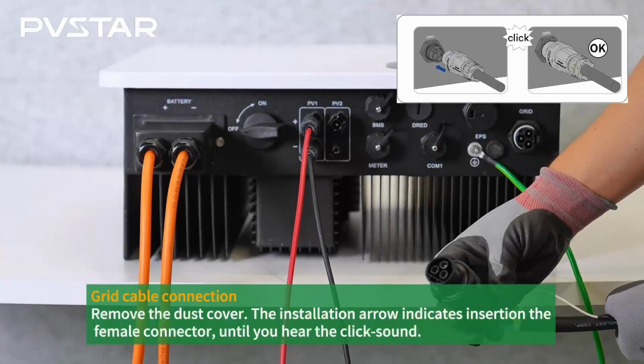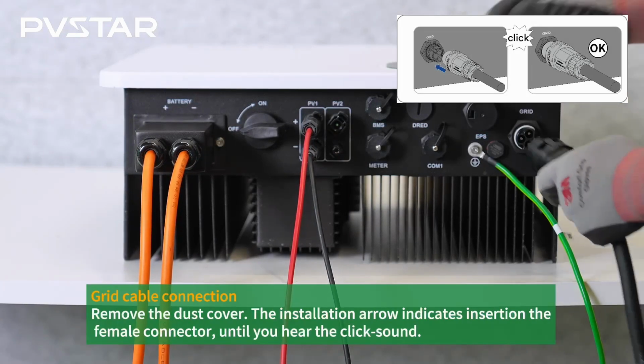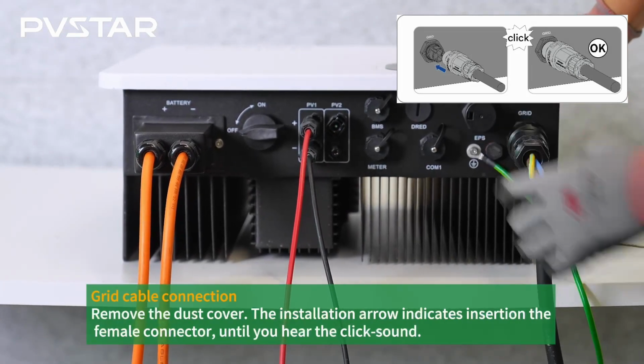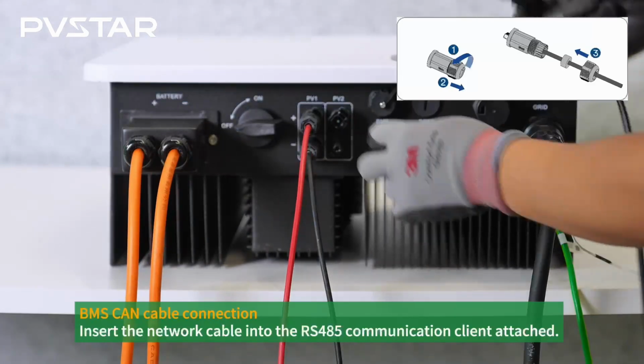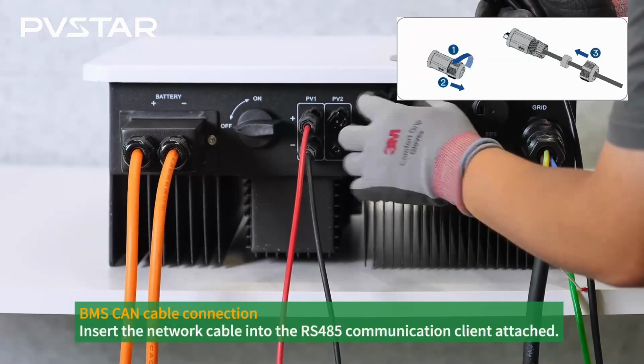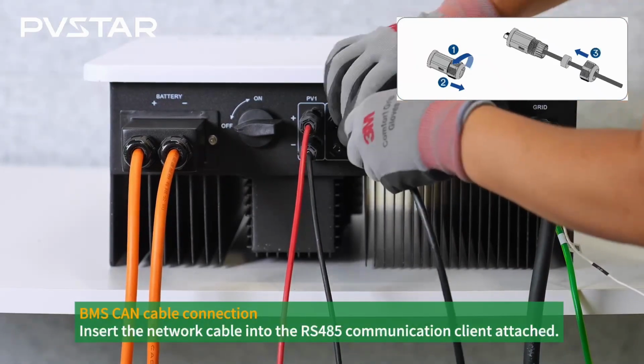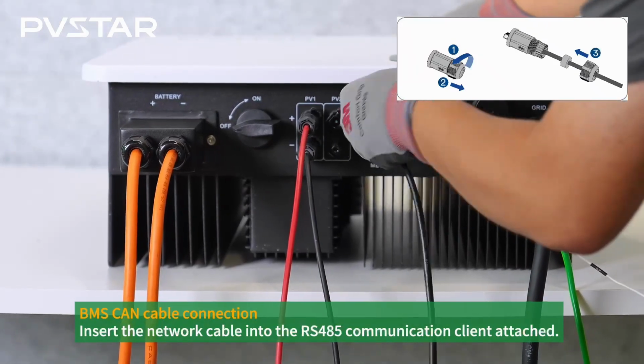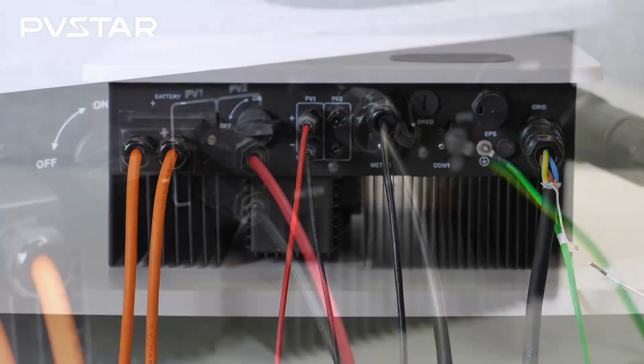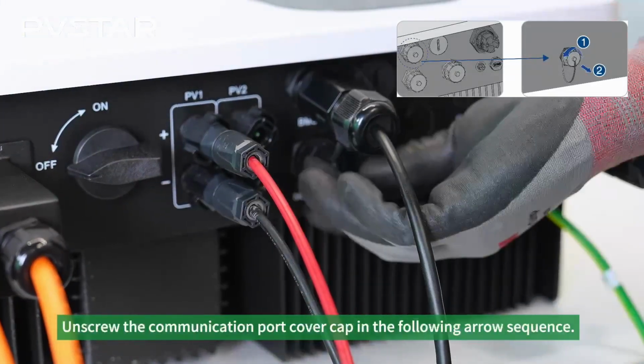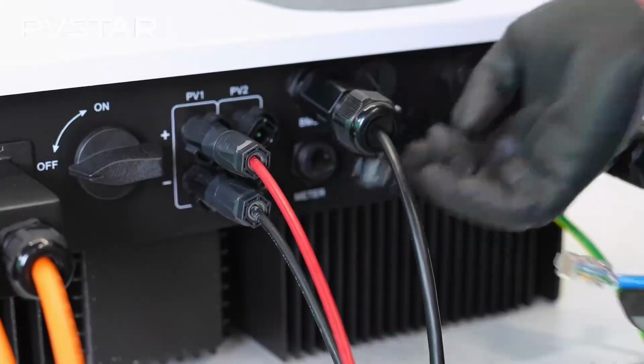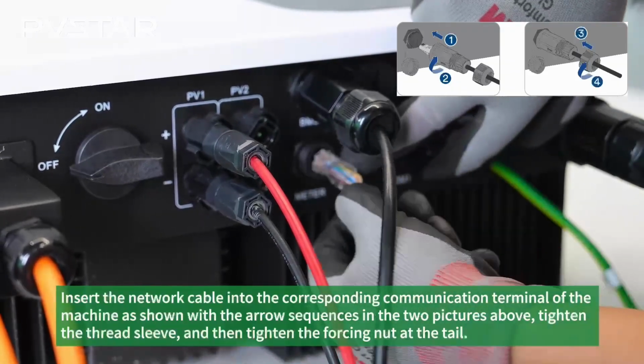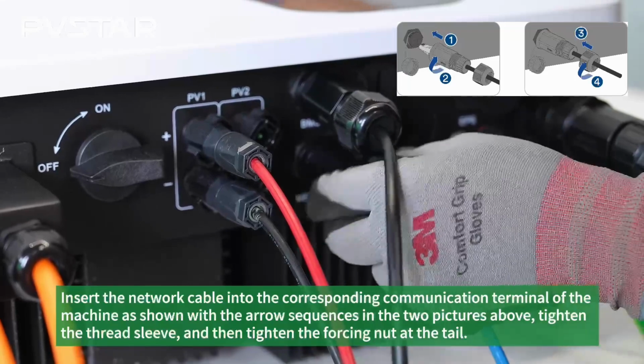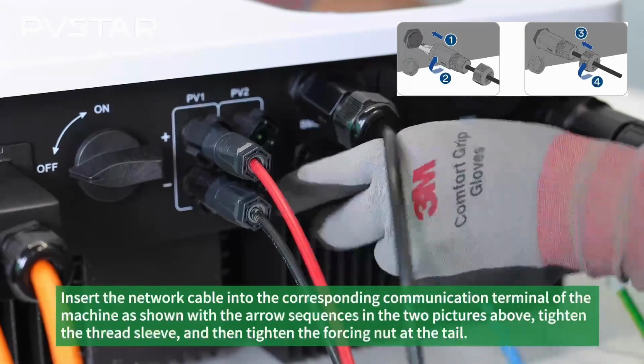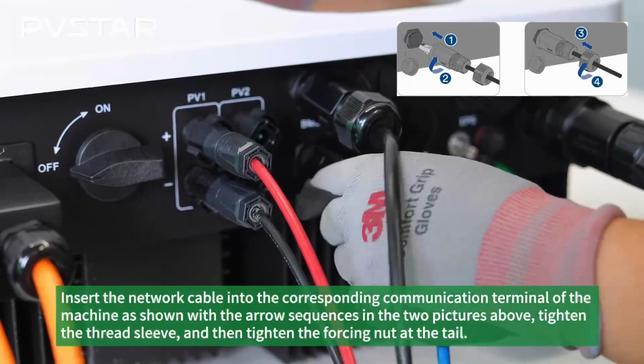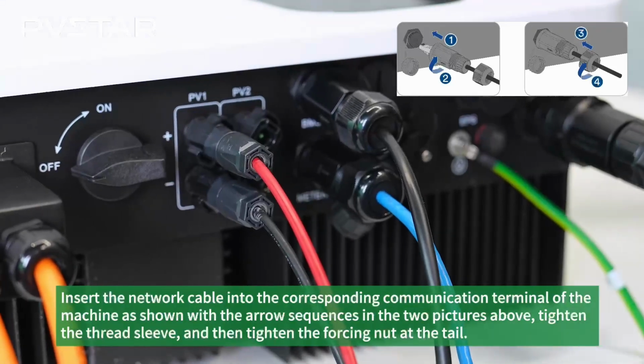Remove the dust cover. The installation arrow indicates insertion of the female connector until you hear the click sound. After finishing the grid cable connection, we will proceed to the BMS CAN cable connection. Insert the network cable into the RS485 communication client attached. Unscrew the communication port cover cap in the following arrow sequence. Insert the network cable into the corresponding communication terminal of the machine, as shown with the arrow sequences in the 2 pictures above. Tighten the thread sleeve, and then tighten the forcing nut at the tail.